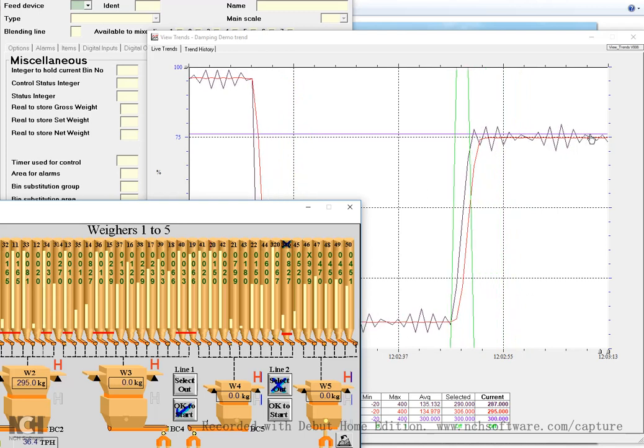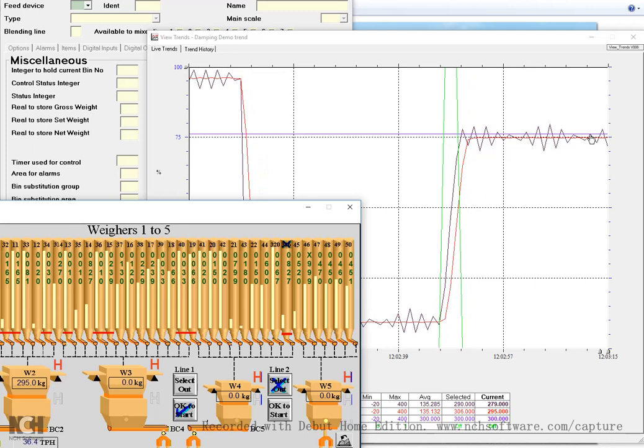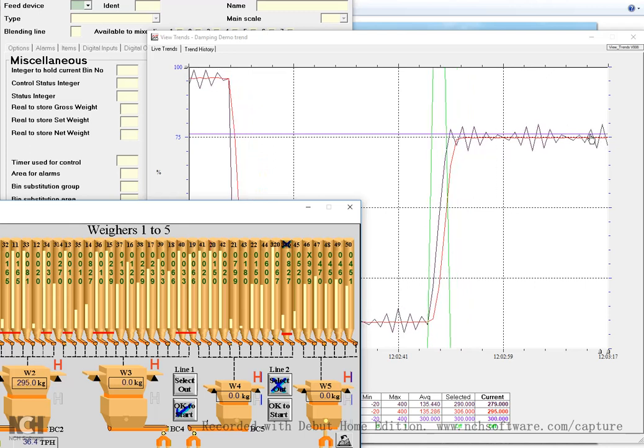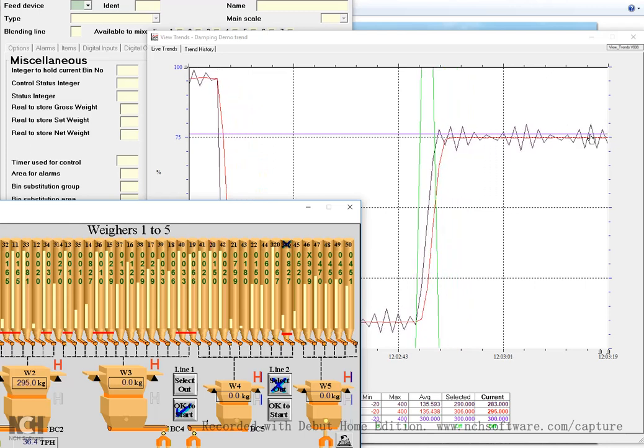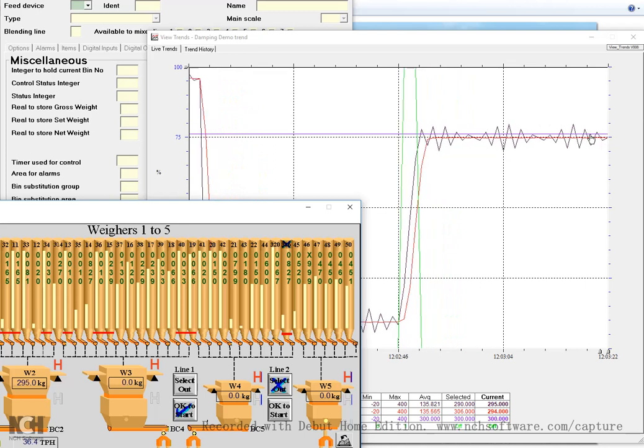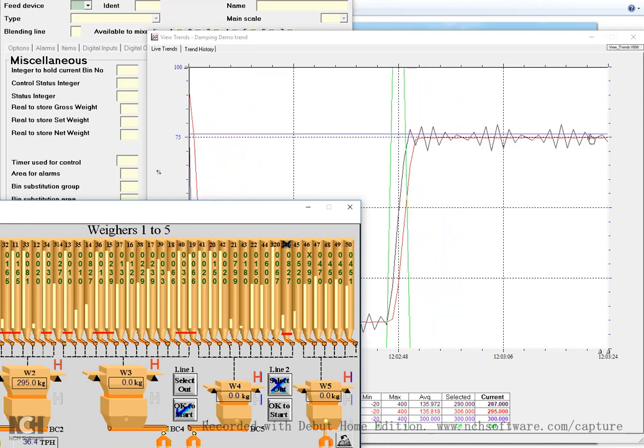Scales vibrating at a higher frequency can have a lower filtering value, but even if you put a very large filtering value in, automatic compensation will eventually adjust itself to a value resulting in accurate weighing.